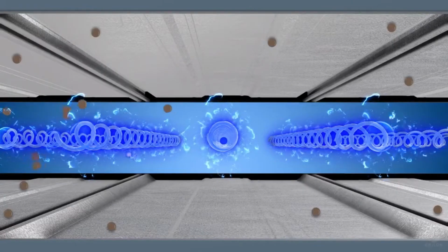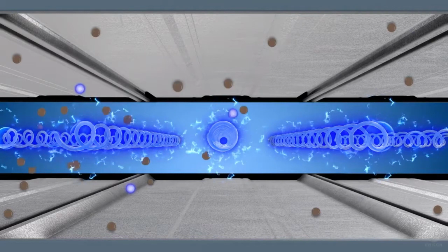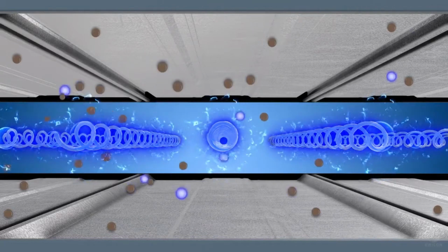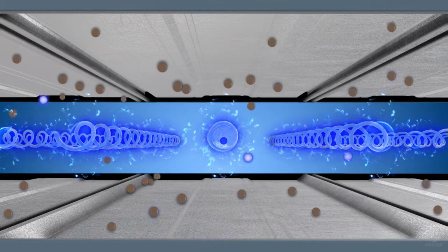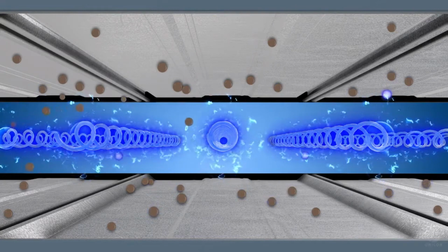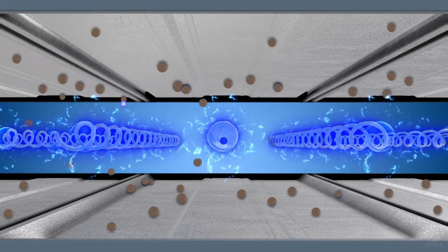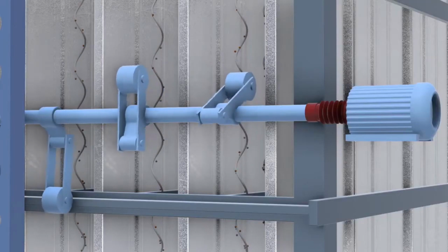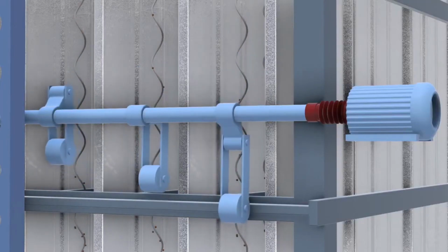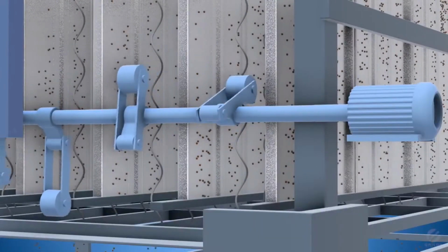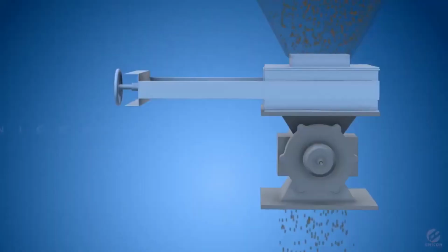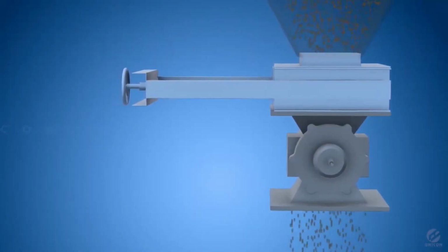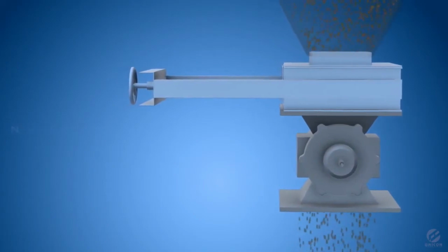The entrained particles are given an electrical charge when they pass through the high voltage electric field. This forces the charged particles to migrate towards the collecting electrodes. The collected particles are then dislodged from the electrodes to the hopper by means of rapping. The hopper is evacuated continuously through the dust handling systems.